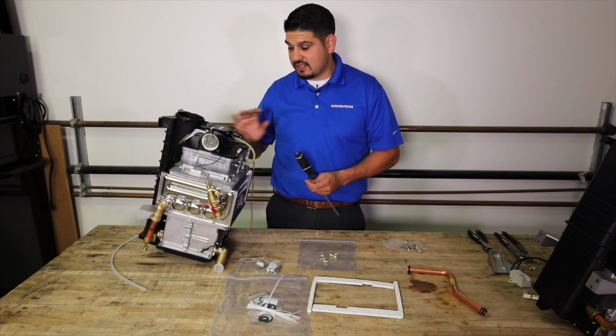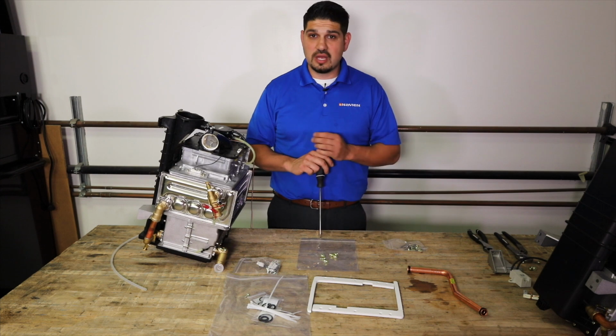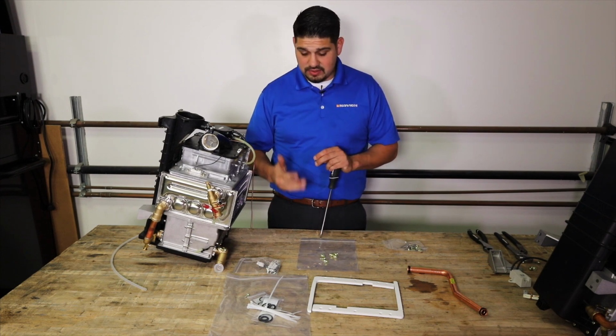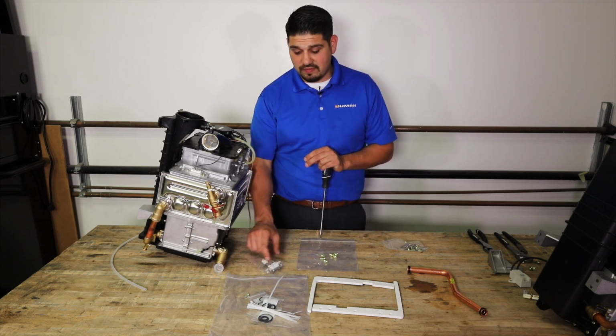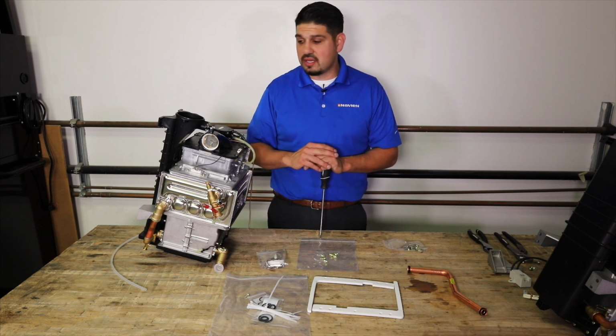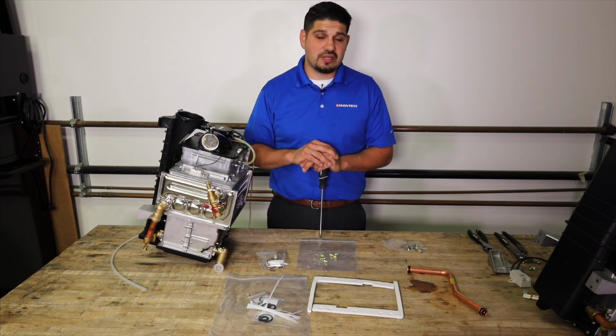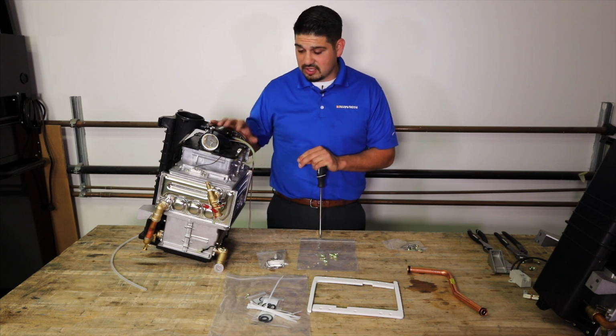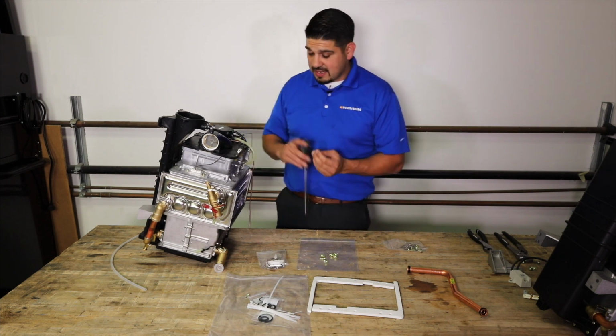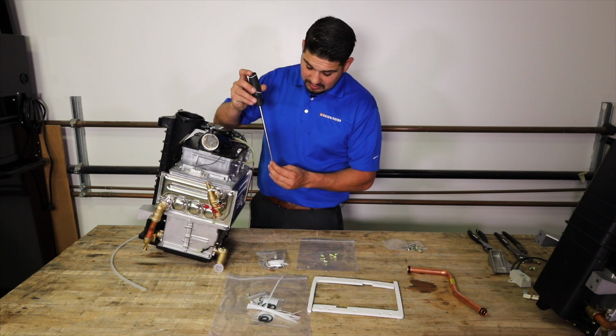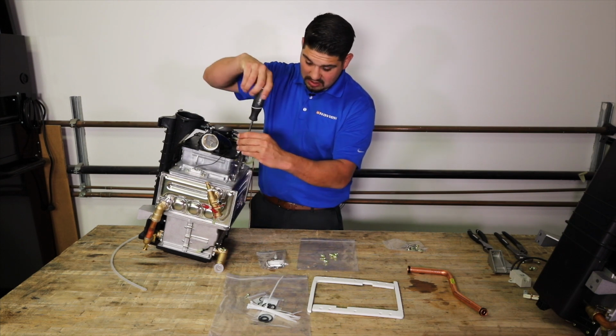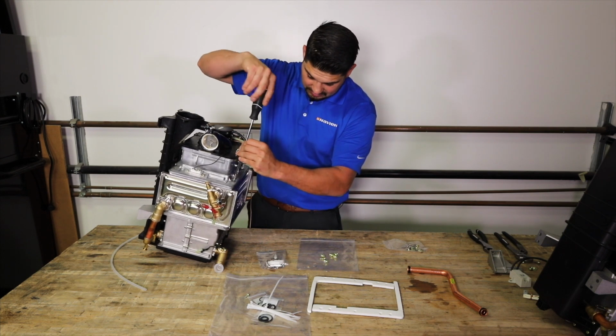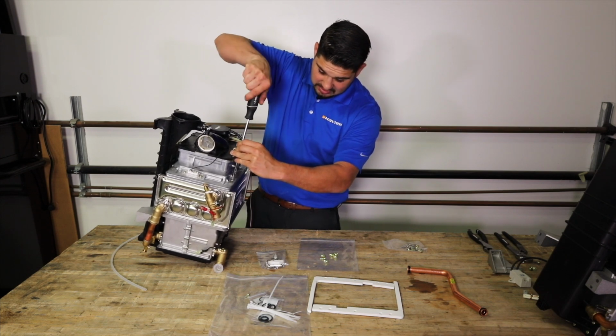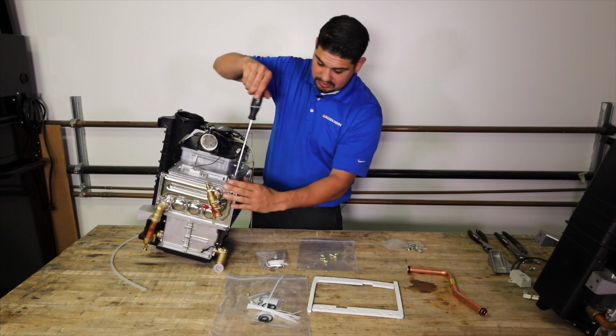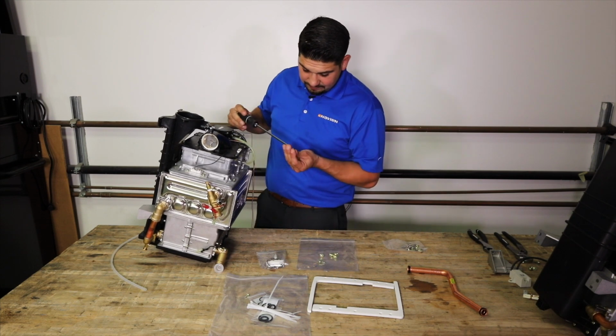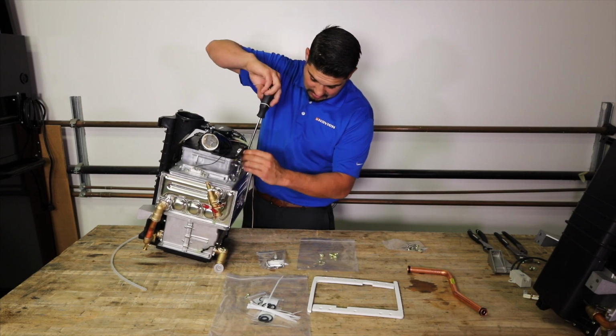So as you're reassembling a lot of your heat exchanger, it's really good practice to go ahead and use all the new equipment provided for you, new hardware, new O-rings, just because they have no wear and tear, they're new. It's just going to give some more life to your unit. So anyhow, I'm going to start just slowly getting these in there. I'm not going to exactly tighten them down. I'm going to just leave it kind of loose so we can still shift it around in case some of these bolts don't align.